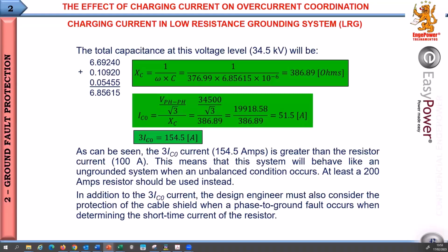our customer thought he was low resistance grounded, but in fact, the system behavior was just like an ungrounded system.